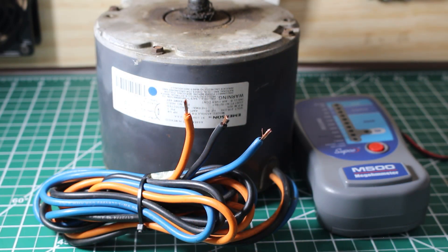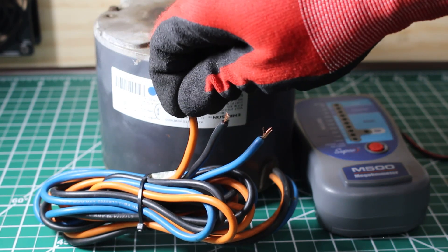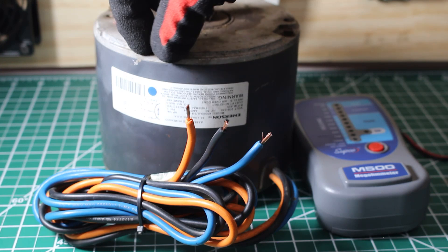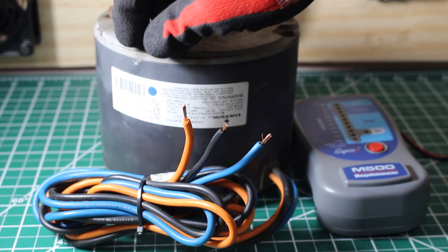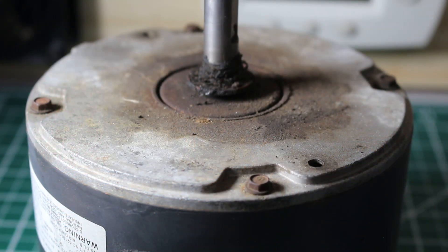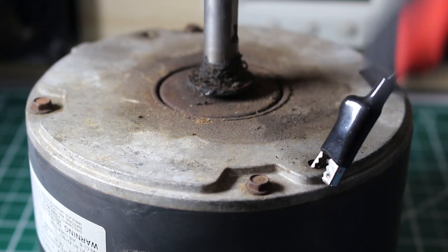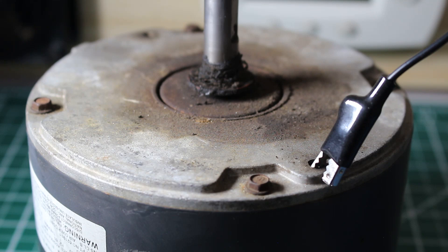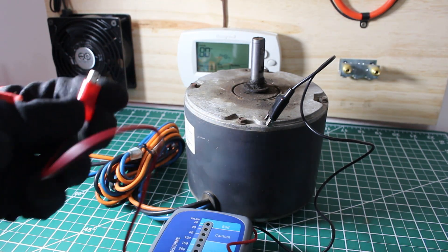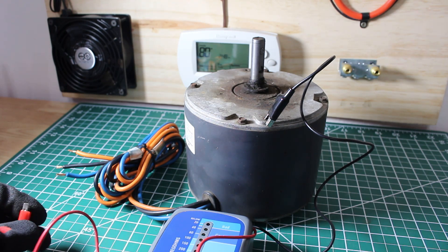Before we begin let me quickly explain what we're actually doing. We're going to check each terminal or lead coming out of the motor relative to a grounding point, which is the casing of the motor. One lead from the megohmmeter stays on the casing at all times, and on the other side we check each wire — one wire to the casing, second wire to the casing, third wire to the casing, and so forth. Make sure the area of the casing you use as a ground is clean of rust for a good connection; use sandpaper or abrasive material if needed.